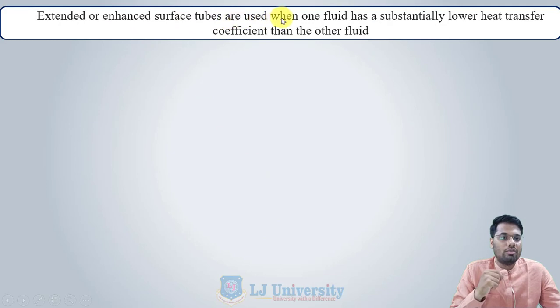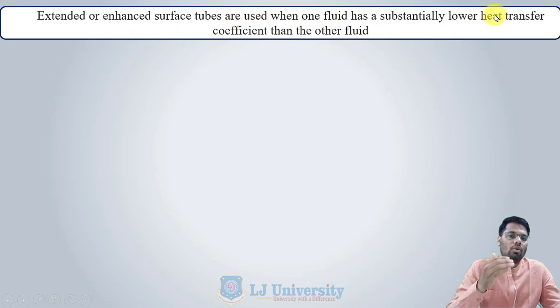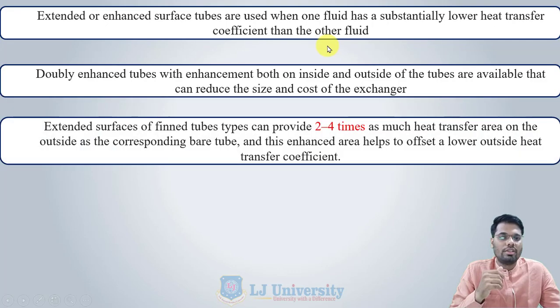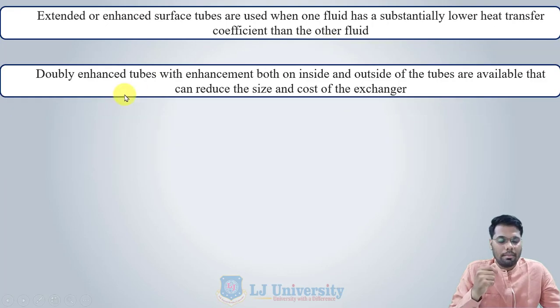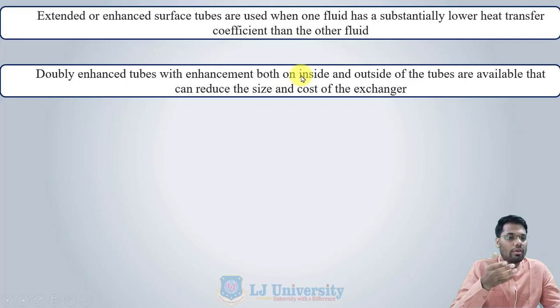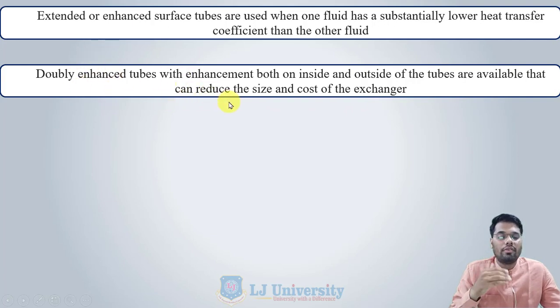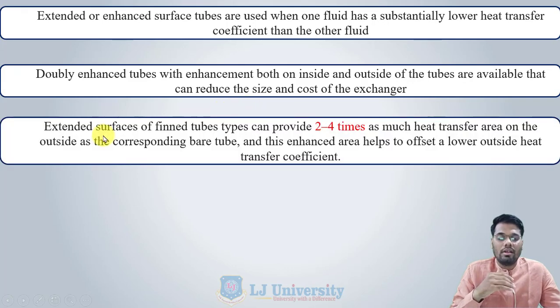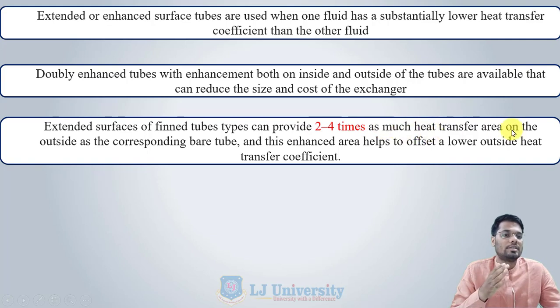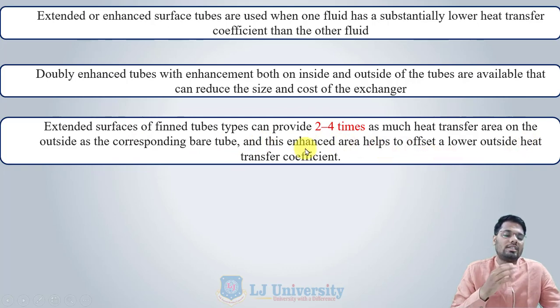Extended or enhanced surface tubes are used when one fluid has a substantially lower heat transfer coefficient than the other fluid. Doubly enhanced tubes — with enhancement both on the inside and outside — are available and can reduce the size and cost of the heat exchanger. The extended fin tube surface can provide two to four times as much heat transfer area on the outside as the corresponding bare tube, helping to offset a lower outside heat transfer coefficient.